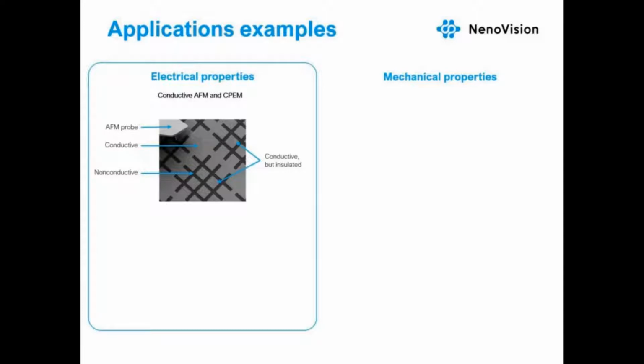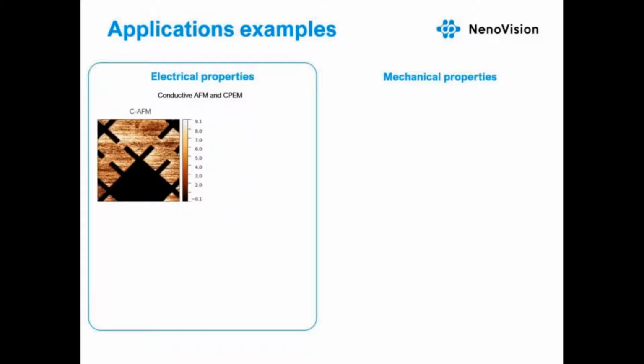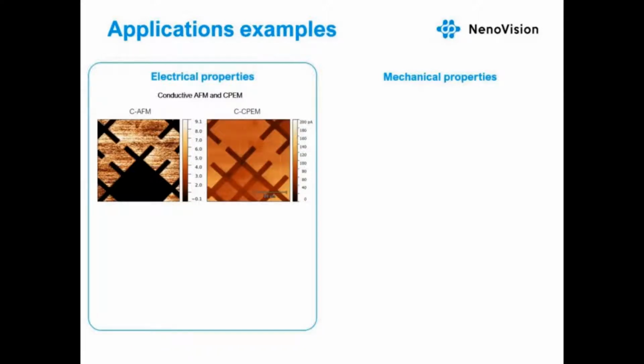So here I'm going to show you some of the most common measurement modes for characterization of material electrical and mechanical properties. So let's start with the electrical properties, and namely with conductive AFM and conductive CPEM. And for that I'm going to use sample where silicon is covered by gold, and the gold creates areas that are conductive, non-conductive, and some of them are conductive but insulated. So if you will do the standard conductive AFM, we will be able to image only the areas that are conductive. However, we can take advantage of the close proximity of the conductive AFM tip to the SEM E-beam, and we can use this E-beam as external source of electrons. And that will enable us to image also the areas that were conductive but insulated.